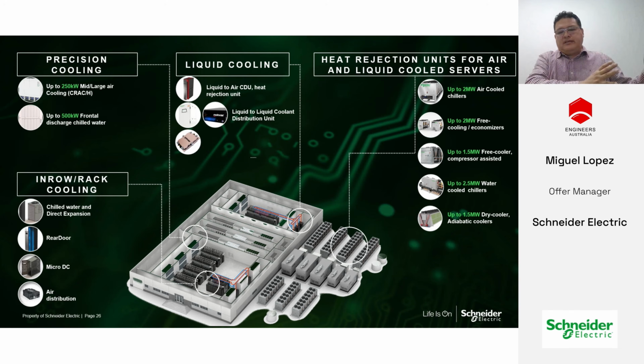As we just saw, thanks to the ASHRAE Technical Committee 9.9, which particular outdoor heat rejection should be deployed as of 2025, and whether we need to think forward to 2026, 2027, knowing that the chiller life cycle ranges anywhere between 10 to 20 years. Should you be future-proofing your liquid cooled system, and how does it harmonize with your precision cooling, in-row cooling systems? These are some of the conundrums that responsible vendors such as Schneider are happy to collaborate on, happy to have those roundtable discussions with your customers.